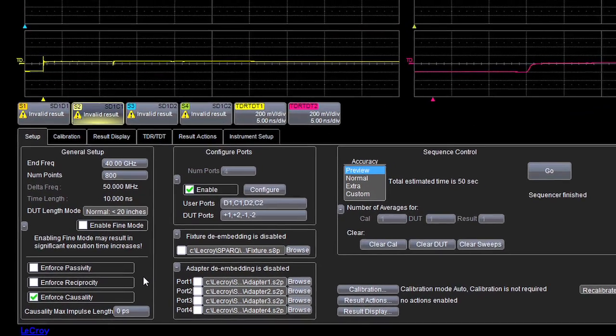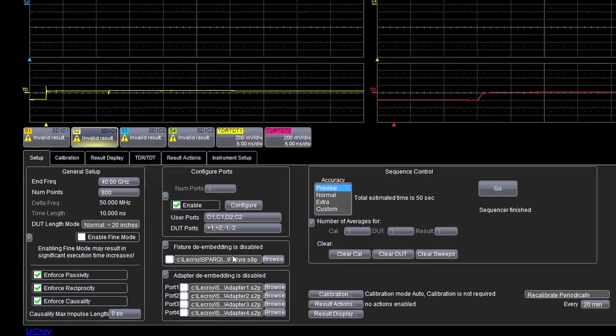The advanced screen has other options, including configuring de-embedding for fixtures and adapters, and for selecting to enforce rules that your simulation software might require. Let's require that the S parameters follow reciprocity and passivity in addition to causality, and then start the measurement by clicking Go.